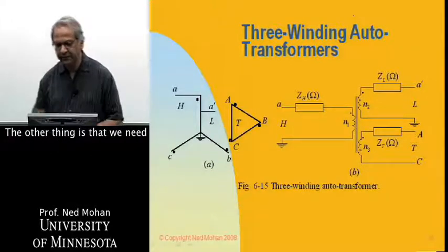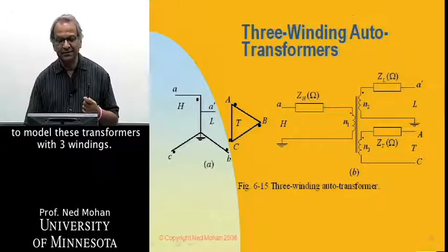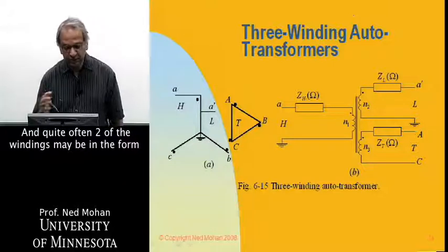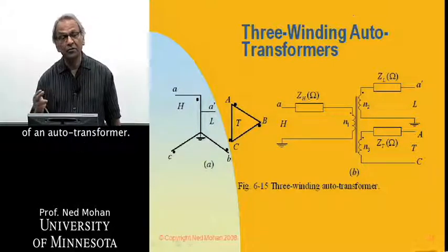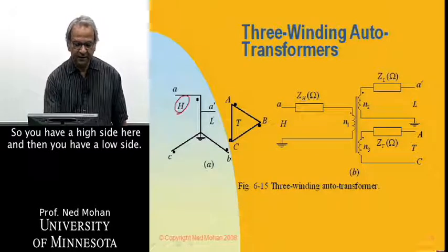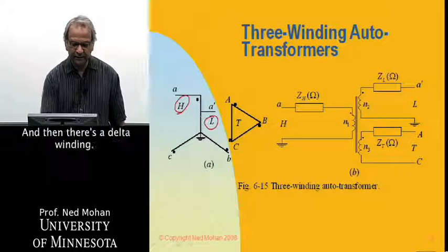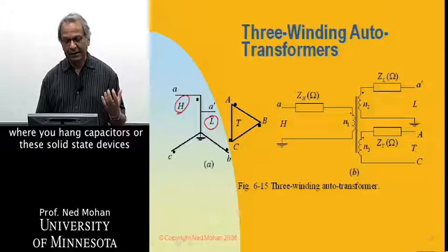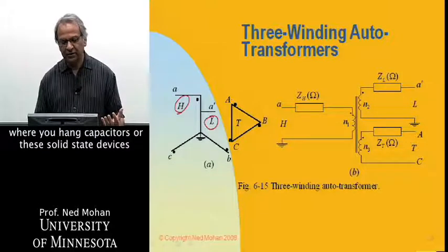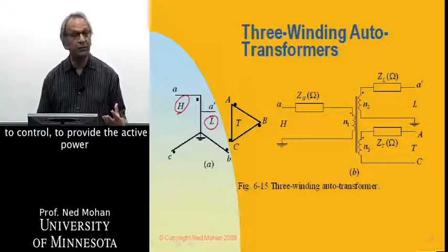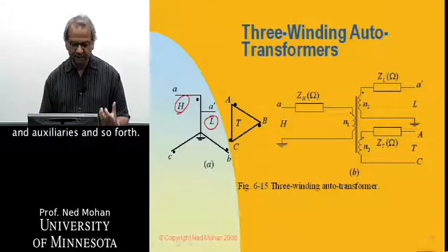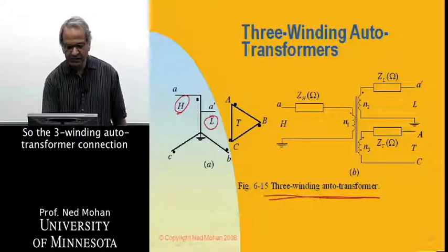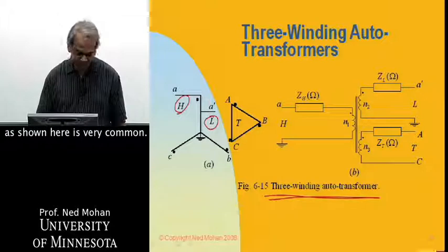The other thing is that we need to model these transformers with three windings. And quite often, two of the windings may be in the form of an autotransformer. So you have a high side here, and then you have a low side, and then there's a delta winding, and this delta winding may be a low voltage winding where you can hang the capacitors or the solid state devices to control, to provide reactive power and auxiliaries and so forth. So this three winding autotransformer connection as shown here is very common.